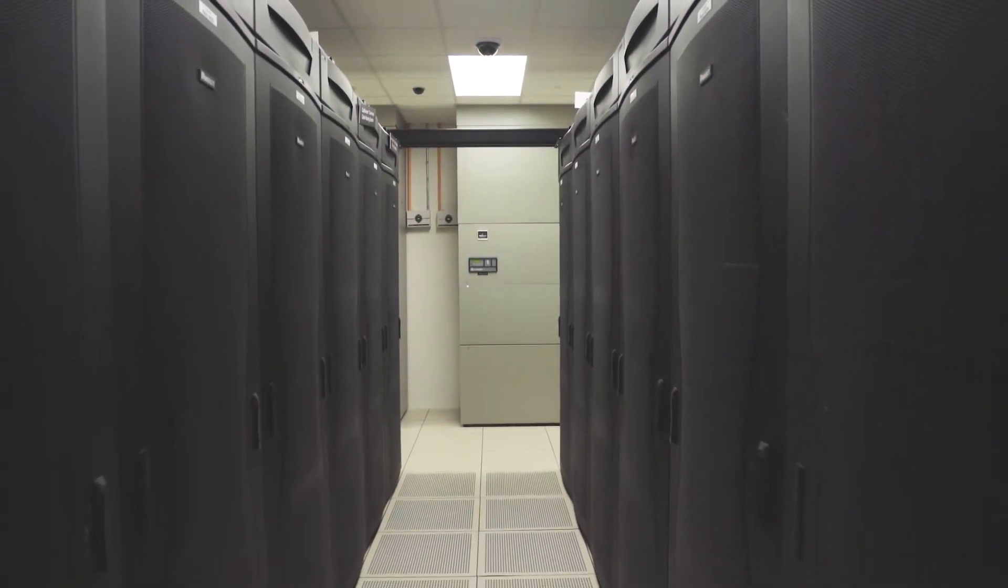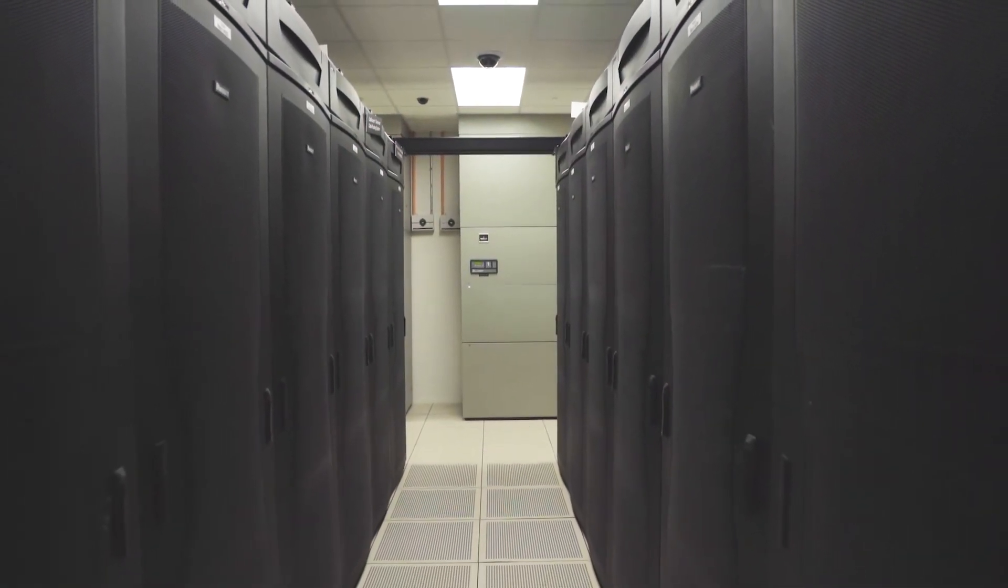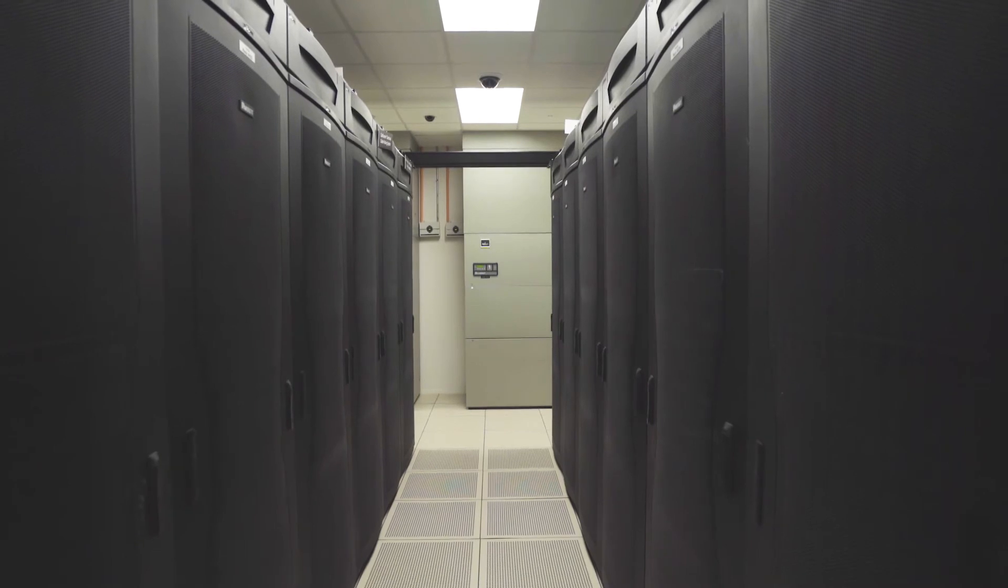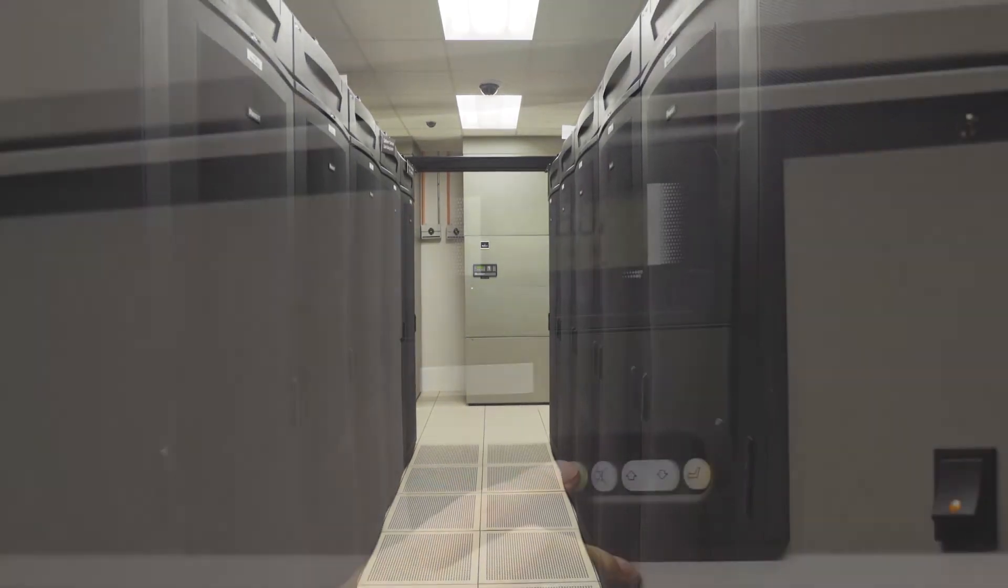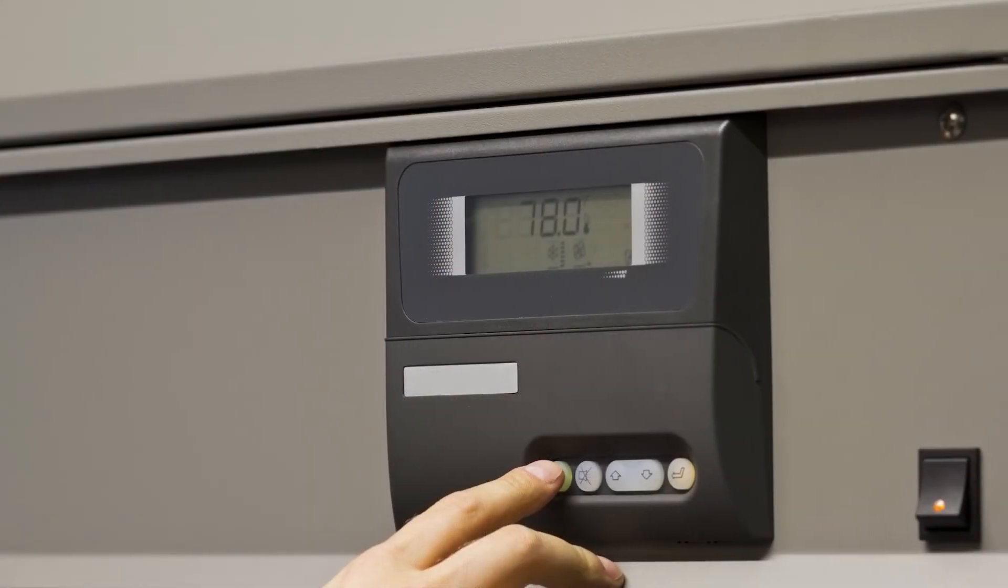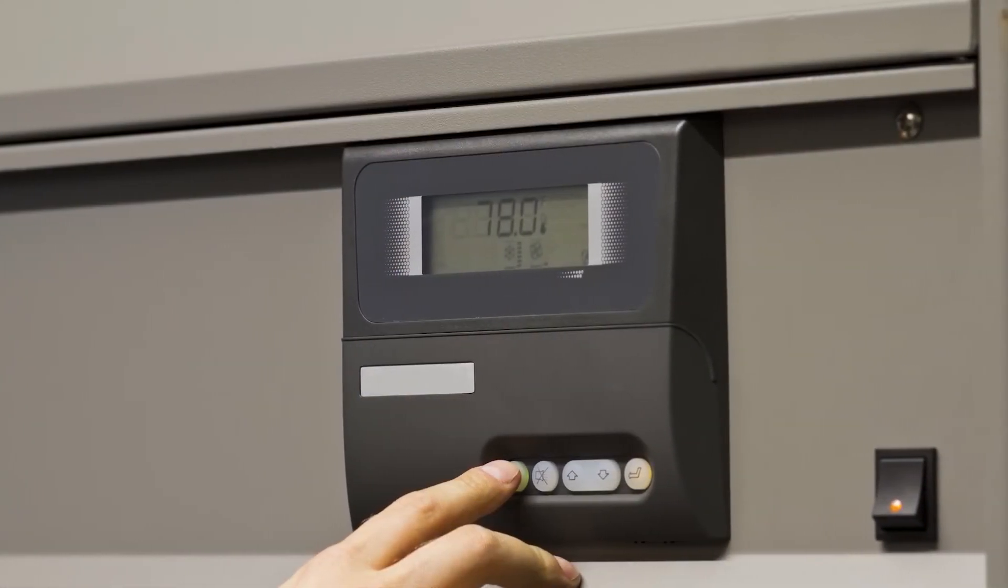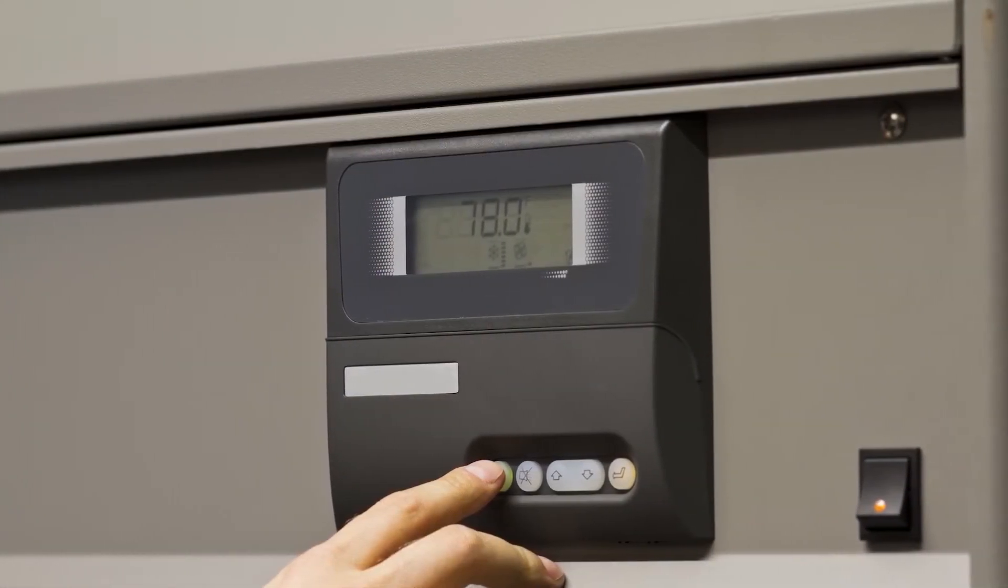Panduit set the target point for the rack inlet temperatures at 78 degrees Fahrenheit, and the control system increased the return air temperature set point to meet this inlet temperature.